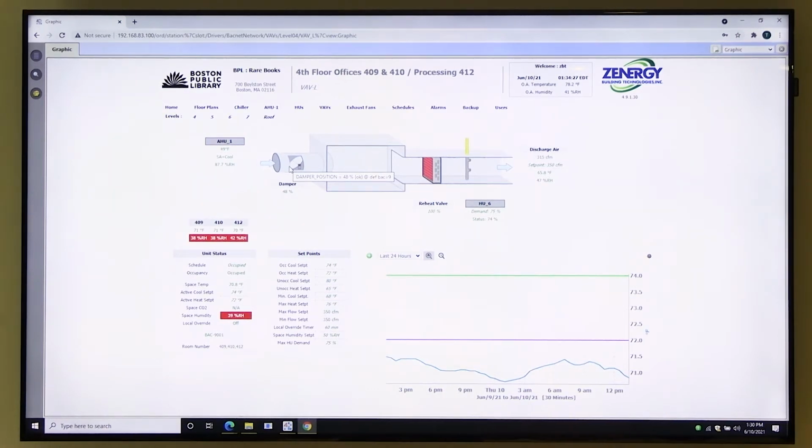Yeah, so the sequence we were given was 50% and alarming at plus or minus 2%, which is pretty tight. That's why everything's an alarm, because you're 2% off, which is almost the accuracy range of the sensor itself. So it's really not that useful. If 30 was acceptable, 30 to 50, or if that needs to get reset based on the outside air and what season we're in, that's definitely doable. But we don't want to be generating these nuisance alarms when it's perfectly acceptable for you.